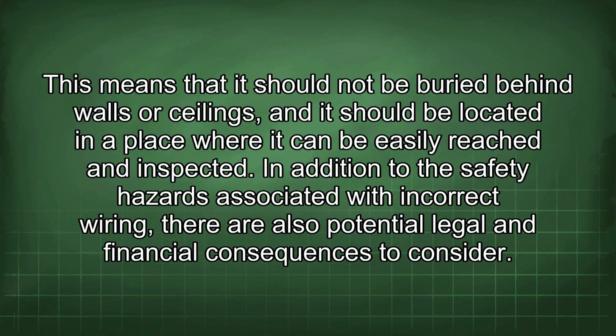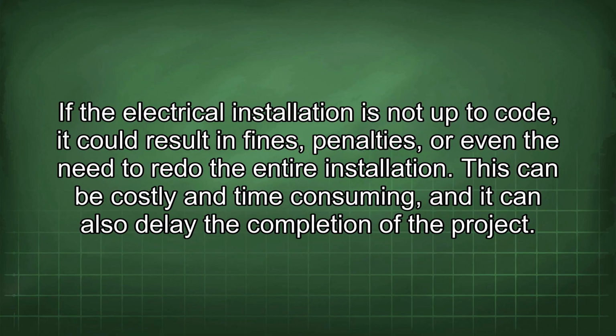This means that it should not be buried behind walls or ceilings, and it should be located in a place where it can be easily reached and inspected. In addition to the safety hazards associated with incorrect wiring, there are also potential legal and financial consequences to consider. If the electrical installation is not up to code, it could result in fines, penalties, or even the need to redo the entire installation. This can be costly and time-consuming, and it can also delay the completion of the project.